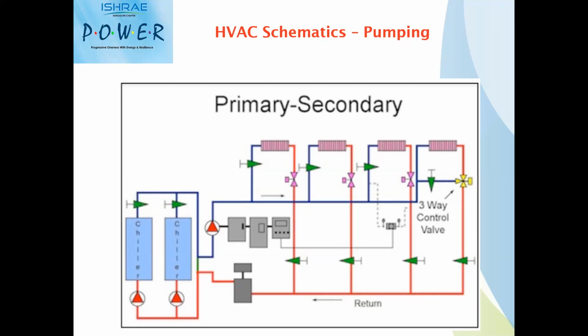And in any variable load application, whenever you are designing the pump, make sure to keep an eye on your variable load profiles, based on which you can select pumps with better efficiencies for your part loads. Most of the time, if your system is operating at lower loads than the design loads, then your operating costs for the pumps are lower by design. So all these parameters are considered for designing the pumps for a chilled water application.